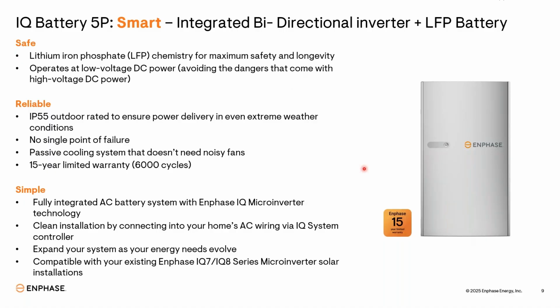If you look at traditional batteries, you have a battery bank. Your hybrid inverters have certain inputs. If you are using a small inverter, it is like 60 volt or 120 volt, and it keeps increasing to 240 volt, and it goes to 320 volts. As your hybrid inverter values increase, your DC voltage increases. Here you will see there is no DC exposed to you. In traditional batteries, you make stackings of batteries and connect minus, plus, minus, plus, positive and negative, and at the end you achieve that certain voltage limit. It depends on which type of hybrid inverter you are going to use and what the input DC voltage range is. Accordingly you connect your batteries.